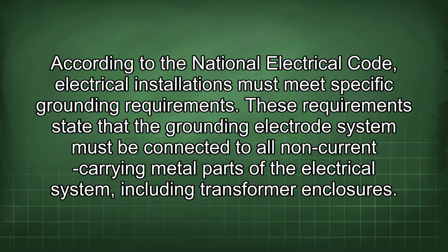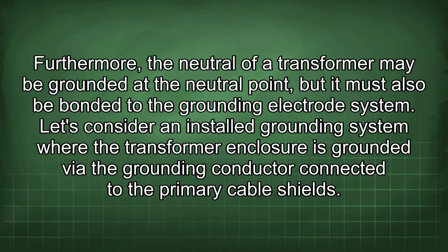According to the National Electrical Code, electrical installations must meet specific grounding requirements. These requirements state that the grounding electrode system must be connected to all non-current carrying metal parts of the electrical system, including transformer enclosures. Furthermore, the neutral of a transformer may be grounded at the neutral point, but it must also be bonded to the grounding electrode system.